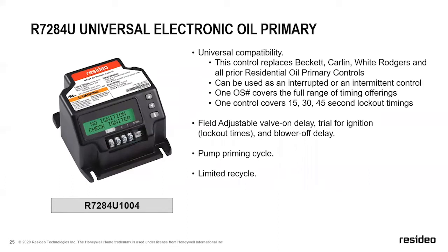Pump priming cycle is super important. If you've ever had a customer or serviced someone that ran out of oil, you know that if that device tried to run without any oil, it's going to get air in the line, and that can be problematic to try to purge out. We've included a pump priming cycle, so when you go for a trial for ignition, you press that up arrow and hold it in, and it's going to add timing up to, I believe, 9 minutes of pump priming. So it'll continuously run that pump to where you can bleed out any air until you get a full column of liquid or oil coming out, and get your customer back up and running. And we also have a limited recycle. So that is our R7284U control. Really easy to set up, and I highly recommend you get your hands on one and get it on the truck.